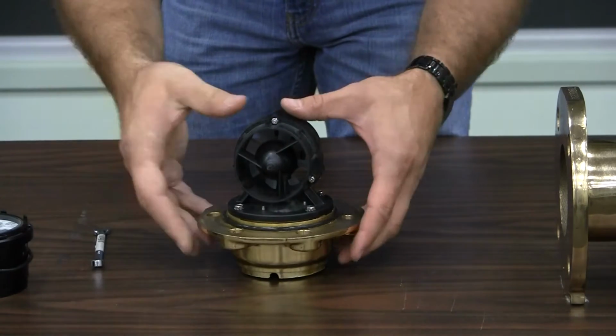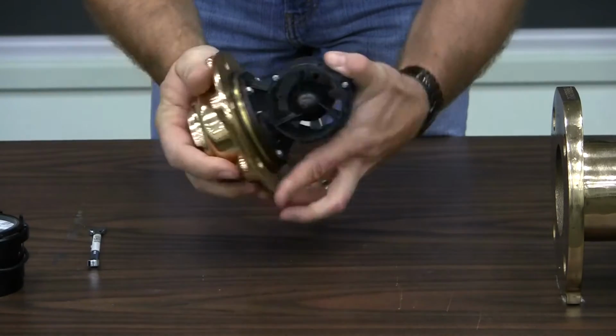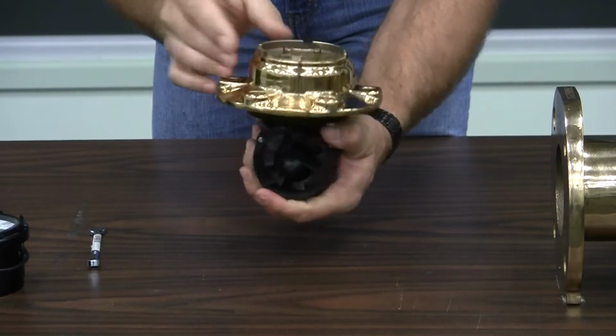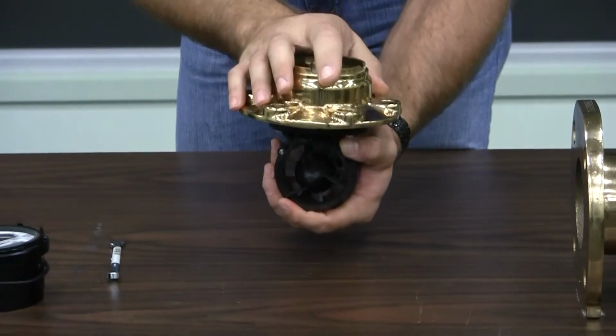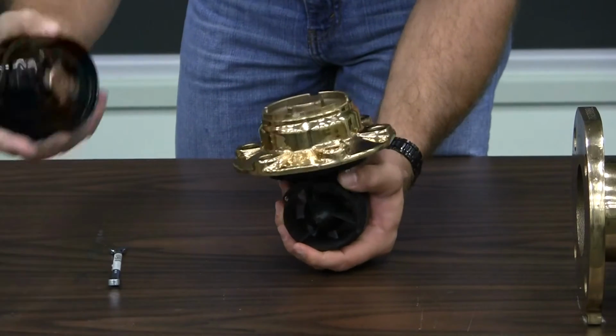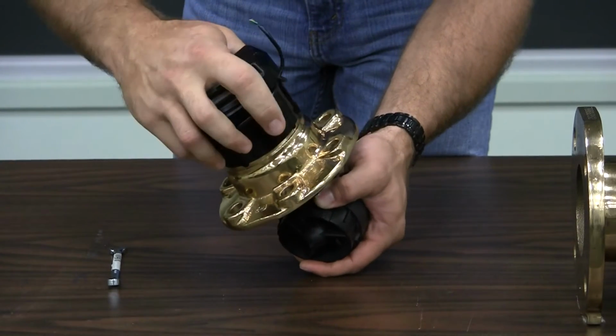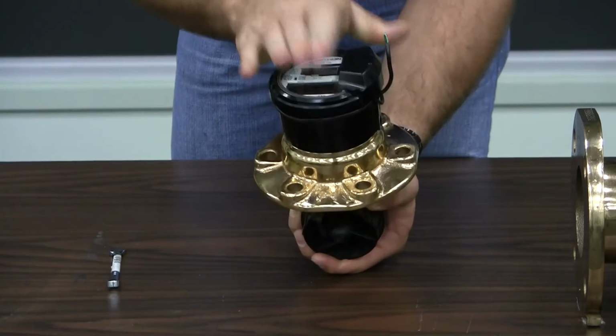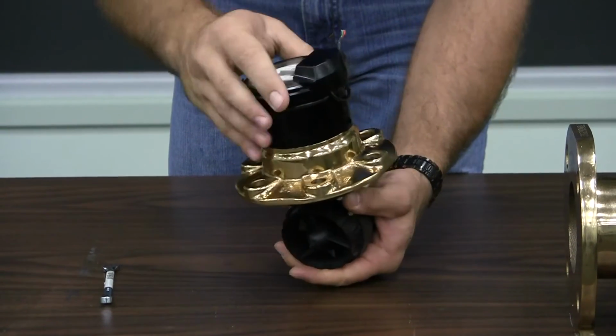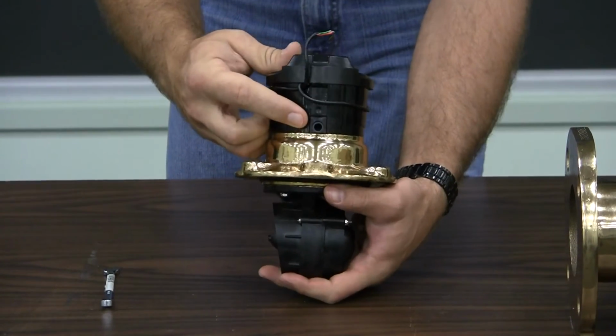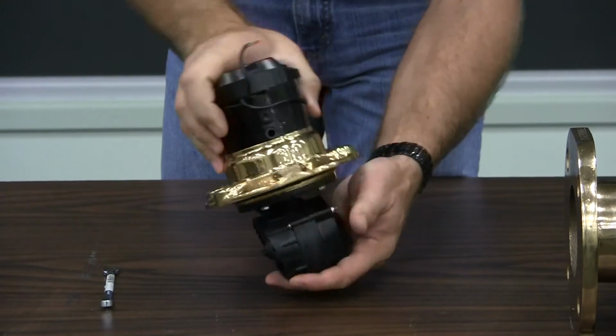Okay, so we've put our 4 bolts inside of our turbine element. We're now back attached to our cover assembly. If you look at this, having the turbine element and the cover, this is what we call our cover assembly. Once I put the register back on the cover assembly, we've got it back up to the level we call unitized measuring element. Now, when you're doing this in practice, make sure you put a seal pin in to secure the register where it cannot be removed.